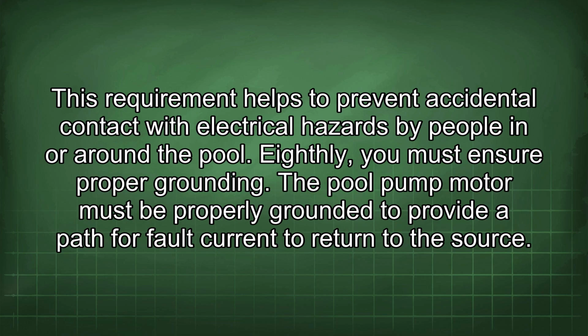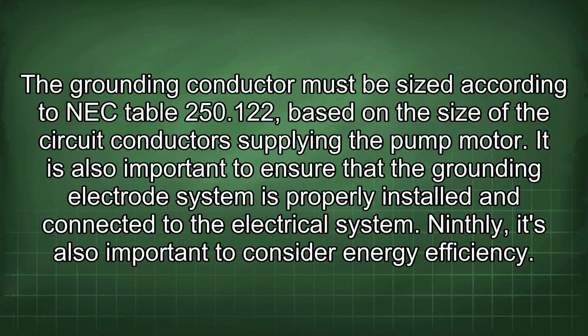Eighthly, you must ensure proper grounding. The pool pump motor must be properly grounded to provide a path for fault current to return to the source. The grounding conductor must be sized according to NEC Table 250.122, based on the size of the circuit conductors supplying the pump motor. It is also important to ensure that the grounding electrode system is properly installed and connected to the electrical system.